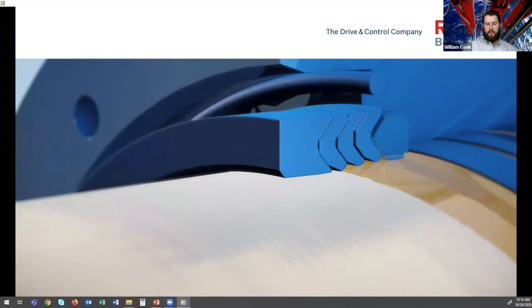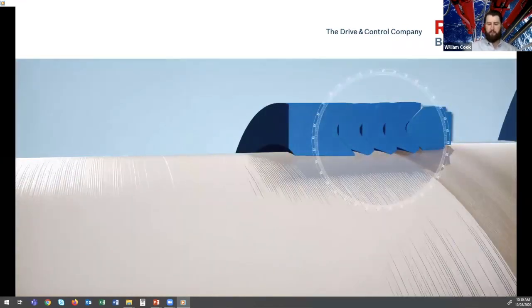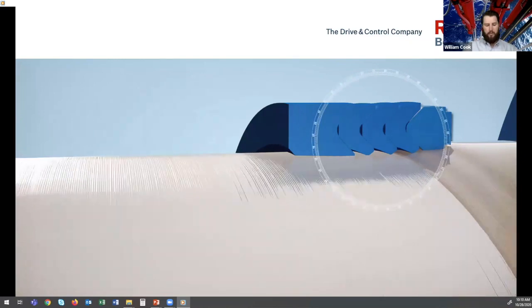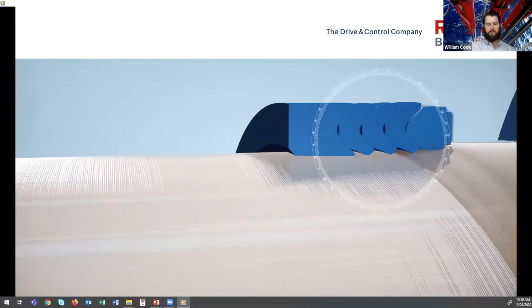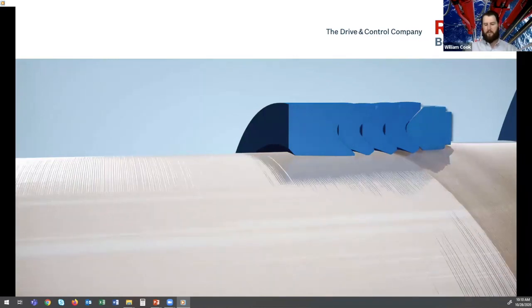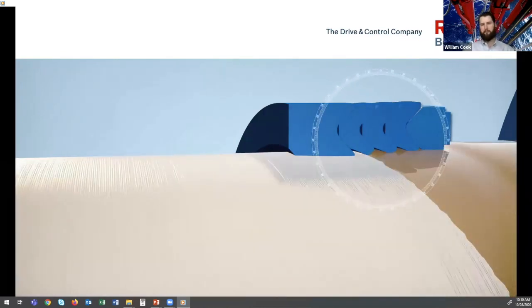When the rod is retracted, the lubrication film needs to be dragged back into the cylinder shell by the rod. To avoid leakage, dirt is blocked by a Bosch Rexroth designed scraper lip while the lubrication film stays intact. The seal cross-section geometry also influences the film. The right seal face design increases the stability of the film.